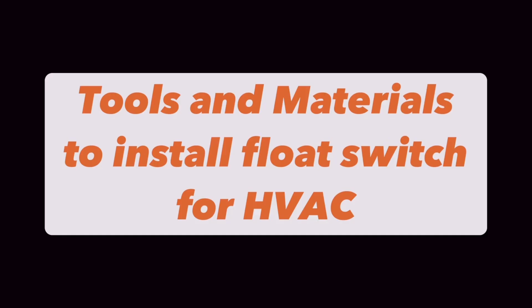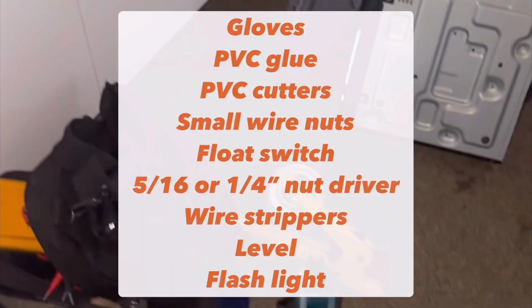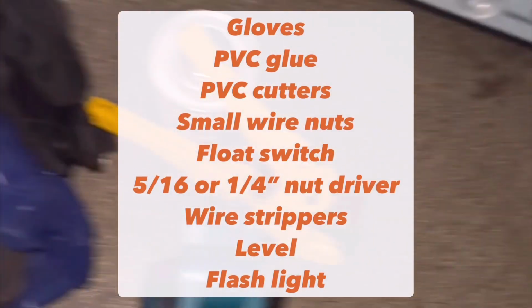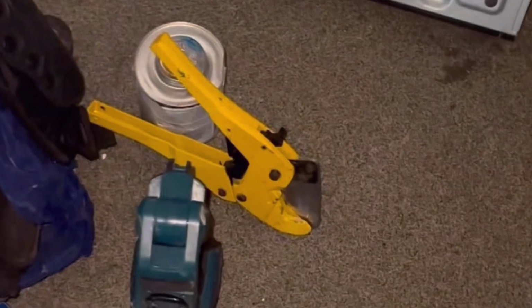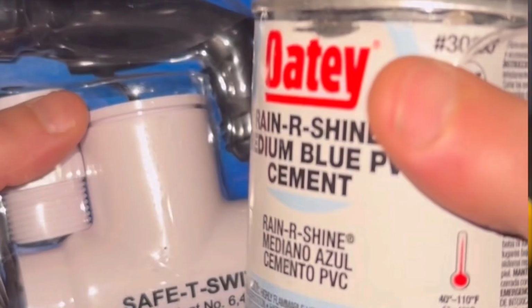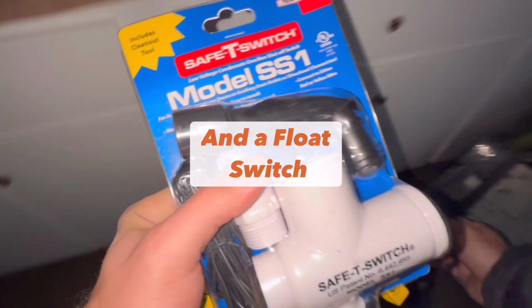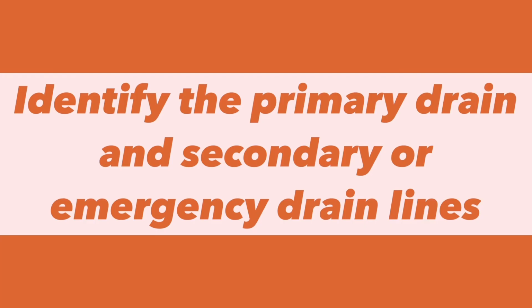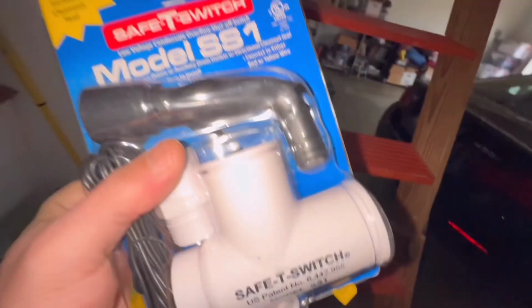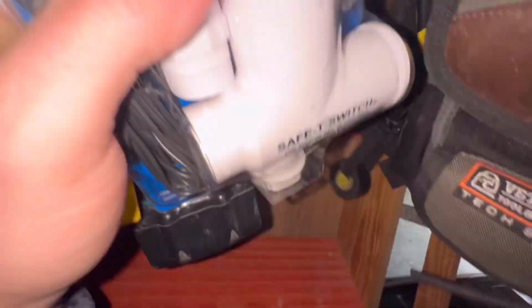First, the tools and materials to install a float switch in your HVAC system. PVC cutters, PVC glue, you'll need some wire strippers, a couple wire nuts, and a float switch. After you have gathered up the tools, the next step is to identify the primary and secondary drains. The secondary drain is also referred to as the emergency drain line.